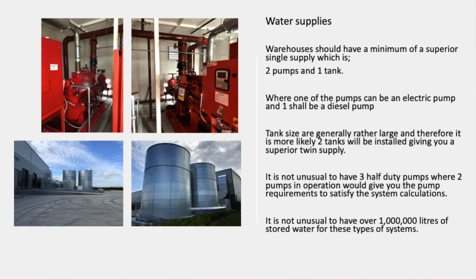This is your typical pump house arrangement, where you've got your tank, you've got some dead water at the bottom, some freeboard at the top, so you get effective capacity. The suction pipe comes along into your pump, that comes up and then comes down to your ICV, which is your installation control valve, and that goes to the system.